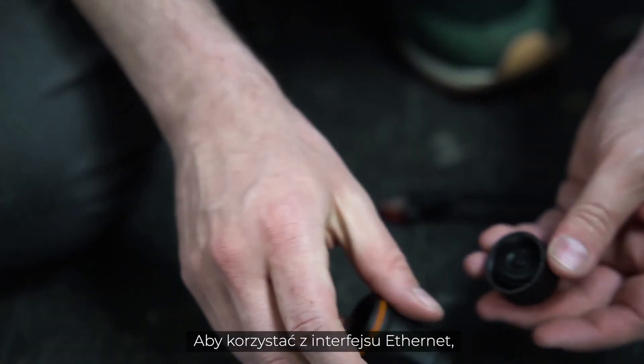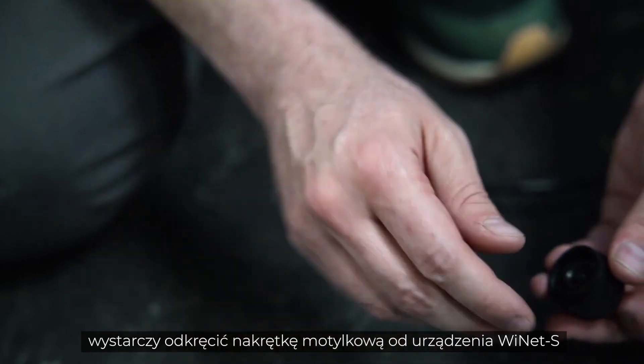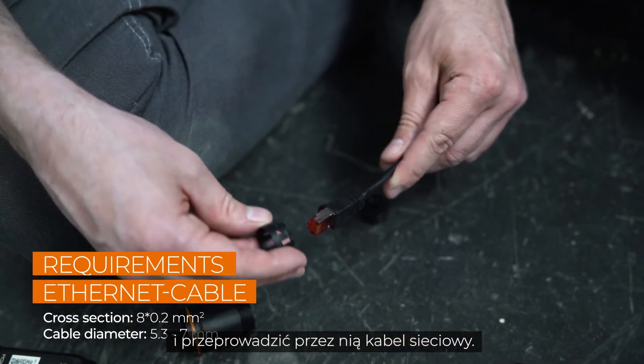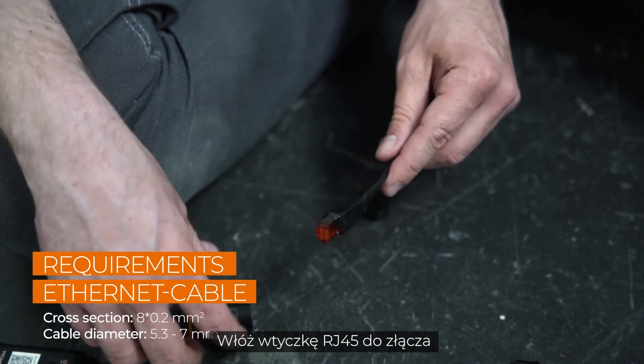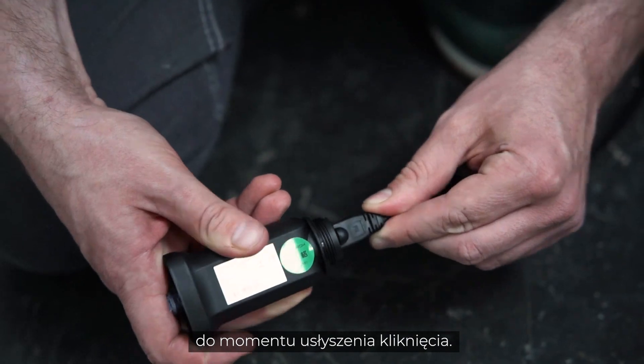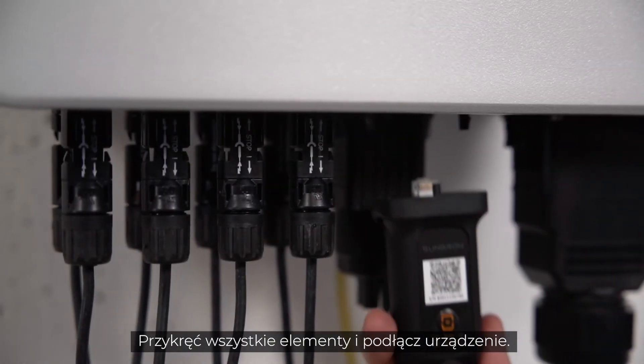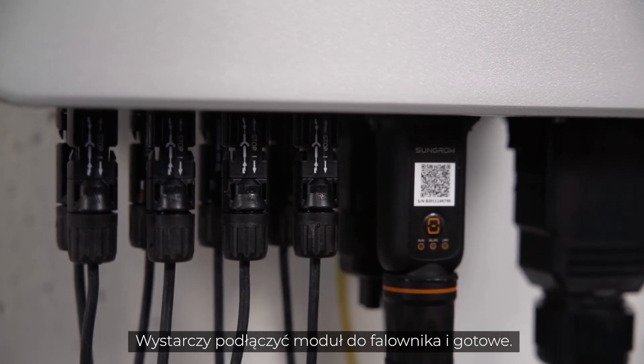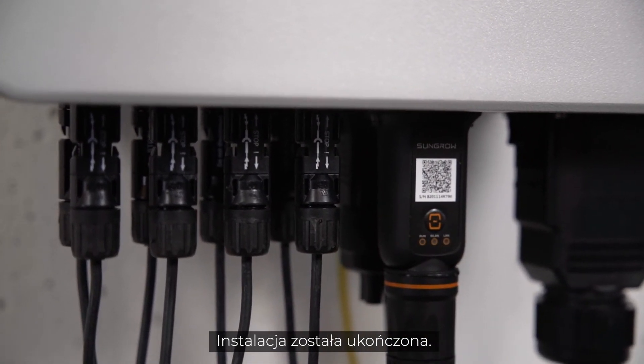The WiNet-S module combines Ethernet and Wi-Fi in one port and is part of the delivery scope. If you want to use Ethernet, simply unscrew the swivel nut from the WiNet-S and thread the network cable through it. Insert the RJ45 plug into the plug connector until you hear a click, screw everything together and plug the device in. If you want to use Wi-Fi, it's even easier — simply connect the module to the inverter.